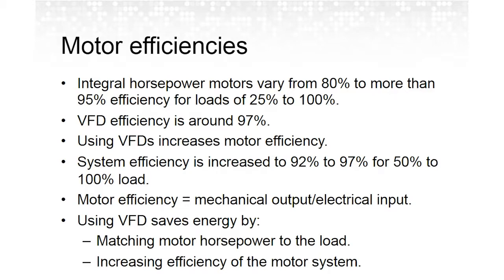Motor efficiencies. The integral horsepower motors vary from 80 to 95% efficient for loads from 25 to 100% of the full load. So say you've got a motor that's operating at 25% of its full load, it's generally around 80% efficient. If the VFD is added, there are losses in the variable frequency drives of around 3% for most applications. So even though you lose 3% of your total application, you still gain because of the significant reduction on your variable torque loads. So therefore your system efficiency is increased from 92 to 97% for a load between 50 and 100%.